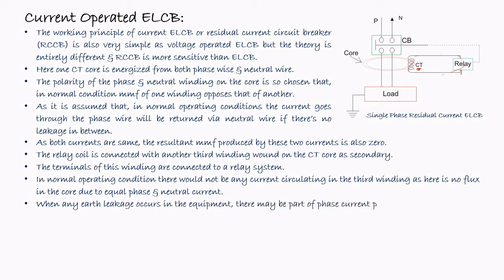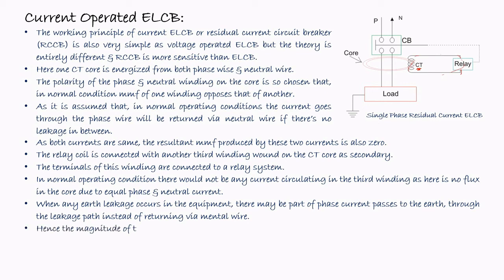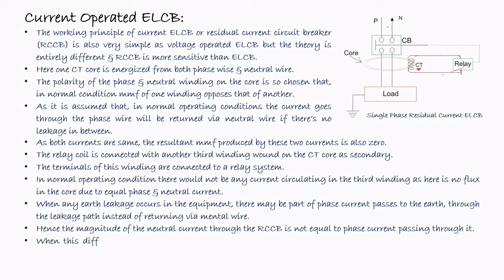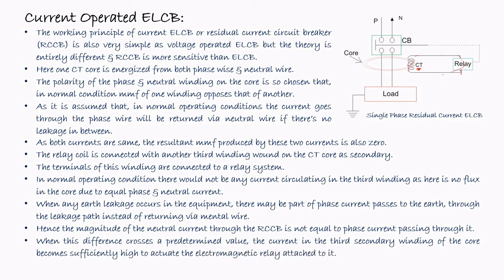But when any earth leakage occurs in the equipment, part of the phase current passes to the earth through the leakage path instead of returning via the neutral wire. Hence, the magnitude of the neutral current through the RCCB is not equal to the phase current passing through it. So if there is any leakage, the current flowing from the phase to the load will not return to the neutral terminal. When this difference crosses a predetermined value, the current in the third secondary winding, that means in the CT winding of the core, becomes sufficiently high to actuate the electromagnetic relay attached to it. That means this coil of the CT will be energized and it will activate the relay part.